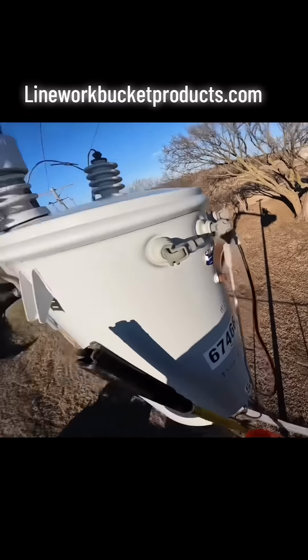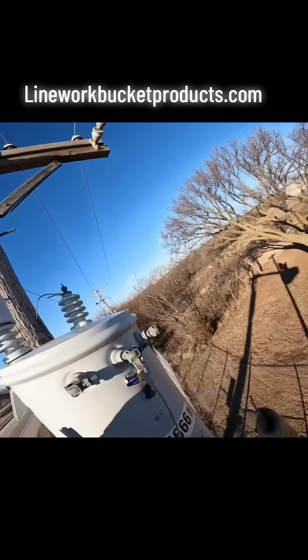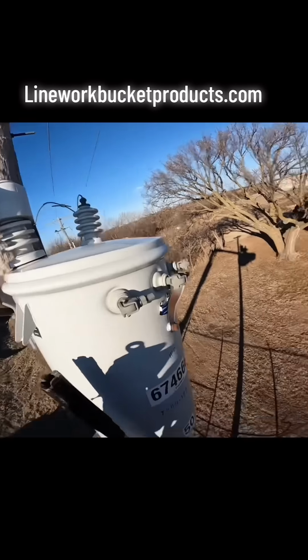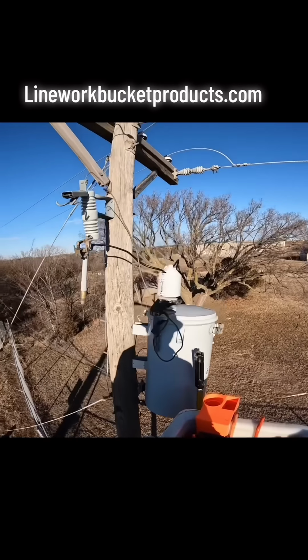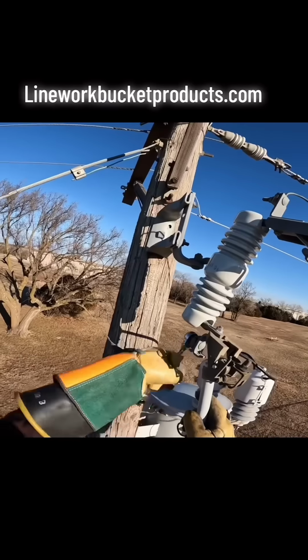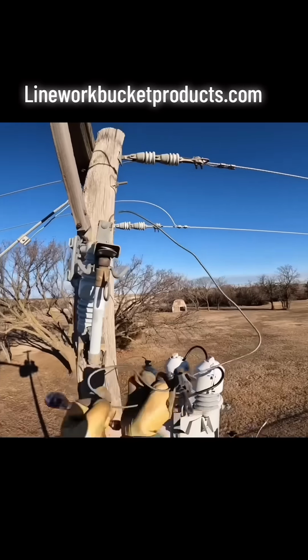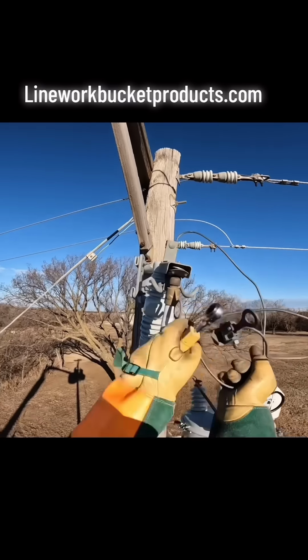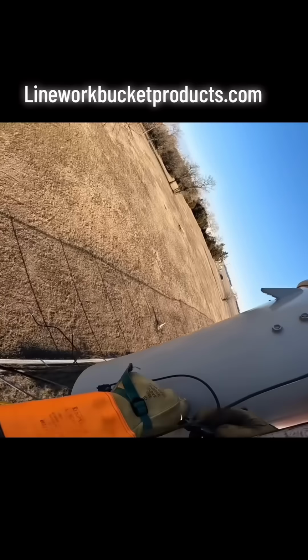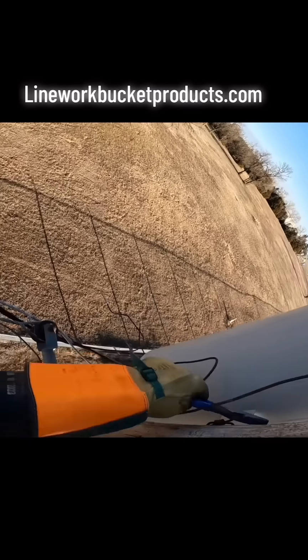The next thing I'm going to do is isolate this transformer, starting with the secondary bushings. I'll take the hot legs out first, then the neutral last. Once I get those secondaries off, I'll go to the primary side and isolate that from the switch. It's good practice to start with the secondary side, just in case there's any backfeed on the transformer.